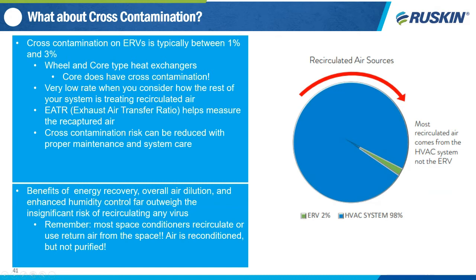Cross-contamination is measured by EATR, which stands for exhaust air transfer ratio. But what I really want to point out on this slide is this graph on the right here. We talked about recirculated air with your rooftop unit at the beginning of this presentation. When we talk cross-contamination, it's very important to limit your cross-contamination with the ERV. However, keep in mind how much of your system is using recirculated air. Most of your recirculated air in your system is not coming from the ERV. In fact, it's only about 2% of the recirculated air in your system on average. So don't focus too much on cross-contamination. The benefits of energy recovery, dilution of the air, and enhanced humidity control far outweigh the risk of recirculating any virus.